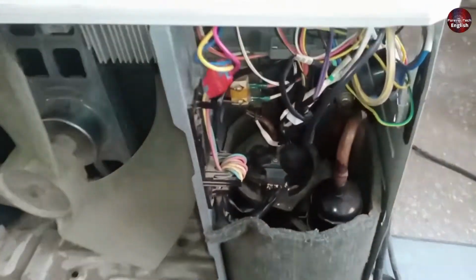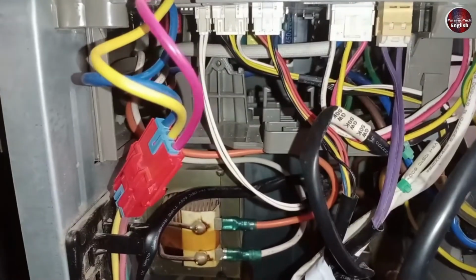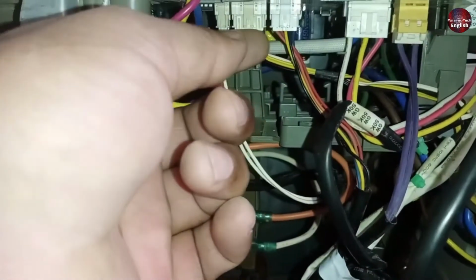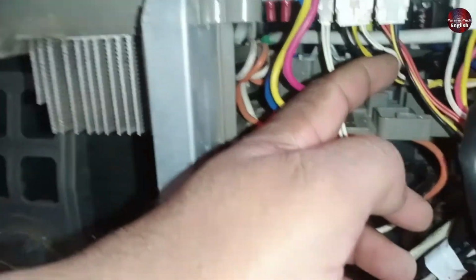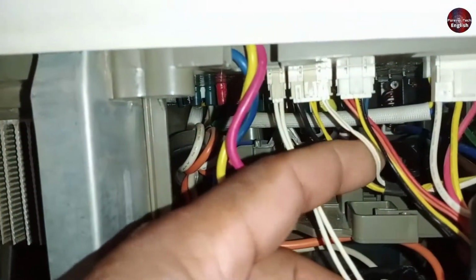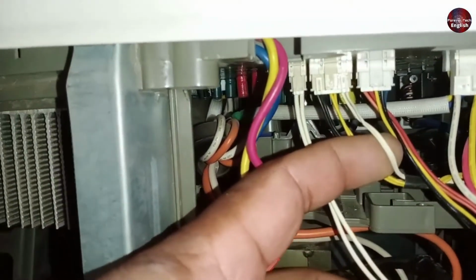Whenever the discharge pipe sensor becomes faulty, it will give you the F5 error. Look here, I'm showing you the connector. In this connector, there is a white wire, which I'll separate and show you. As you can see, it's a bit hard for me to grab, but now I've taken it out. This white wire is for the discharge pipe sensor. Whenever the discharge pipe sensor becomes faulty, the F5 error will show up.